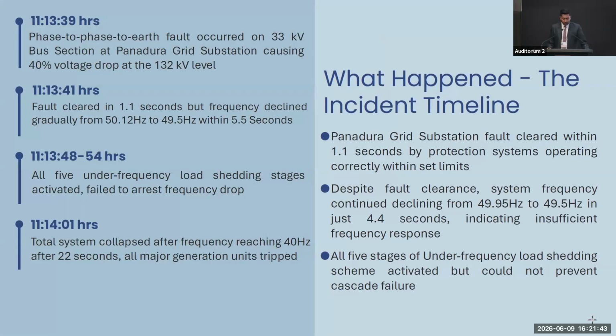So if I come to the sequence of events, the triggering event was identified as a fault at the 33 kV level of a grid substation in the western region of the country. It was found that the system voltage dropped by 40%, followed by another 20% due to this failure. However, this fault at the grid substation was cleared within 1.1 seconds, and the protection system operated correctly and within the set limits. Therefore, this fault should have been cleared as a local failure without impacting the total system. However, this failure cascaded into a total failure. That's why we decided to do an investigation.